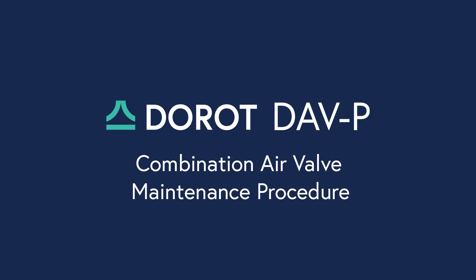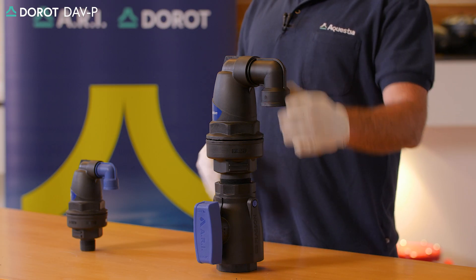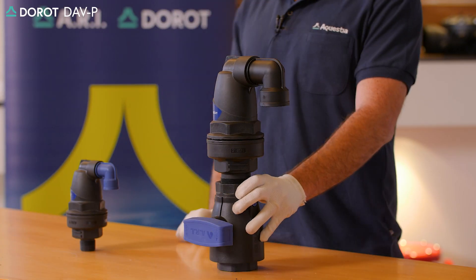Maintenance procedure on the Dorot DAV-P combination 2-inch air valve. We'll start by closing the isolation valve underneath the unit.